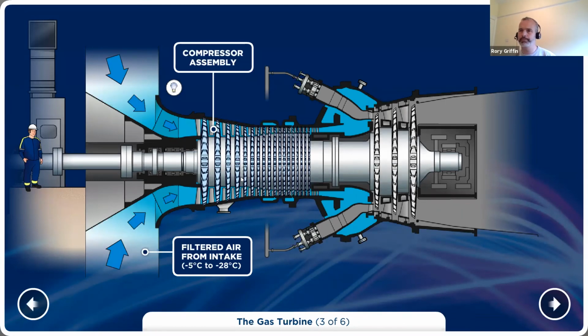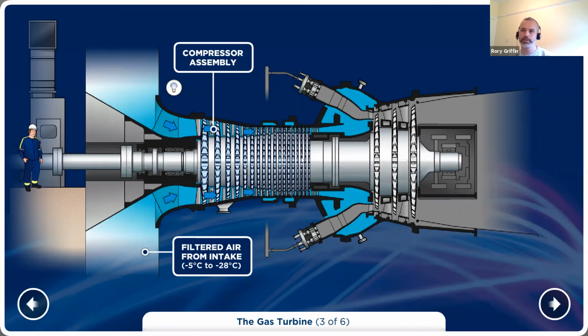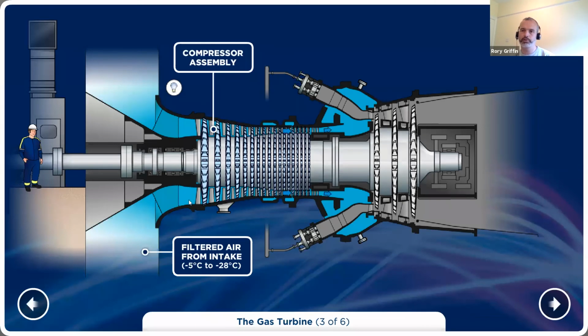The other aspect though, with the compressor, is when you're at 50 hertz, the machine is at 3000 RPM, that's fine. So air is already in the compressor. But if the grid speed suddenly drops, you've lost 30 RPM, you're now taking in air at a lower pressure. The risk is the air that's already in the machine at the higher pressure, you could get a surge. So what happens is on a unit like Whitegate, there's bleed heat. So you're always bleeding some air back into the inlet. And when you get to base load, that closes up. The other thing I should have mentioned is there's inlet guide vanes here as well. So before you get to maximum output, the airflow can be controlled as well through the guide vanes. So through the guide vanes and the bleed heat, you try to minimize any turbulence in the compressor.